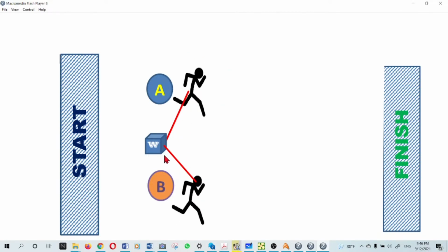If two generators have to share a load and that load is greater than one generator itself can carry, while these two generators are running in parallel, if they are not equally shared, and if the percentage of the load one generator is taking exceeds its maximum working load, that generator might eventually fail.